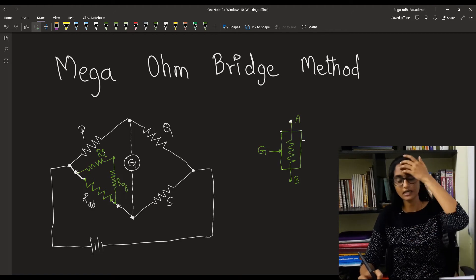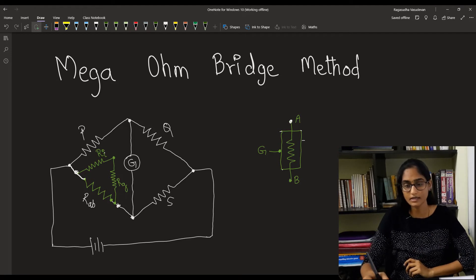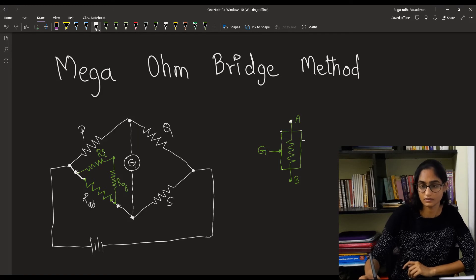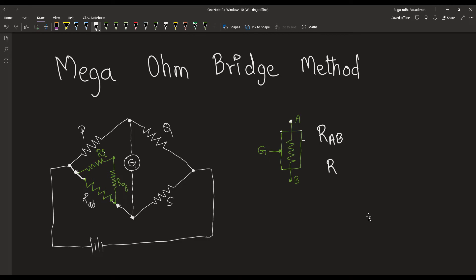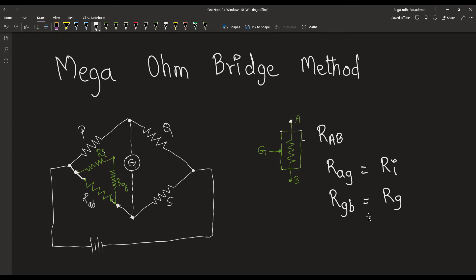Consider that this is the high resistance that you are going to measure, and the terminals A and B are the end terminals of this high resistance. The resistance R_AB is the resistance under measurement, which is connected in the R arm of the Wheatstone's bridge. The resistance R_AG equals the insulation resistance, which is mentioned as R_I. The resistance R_GB equals the guard resistance, or the resistance between the guard terminal and the end terminal of this resistance. When you have a setup like this, you will invariably reduce the value of the resistance R. This is just a modified form of Wheatstone's bridge. If you just plug in this high resistance into the R terminal, you will be facing errors because of the insulation resistance and the resistance between the guard terminal and this resistance.